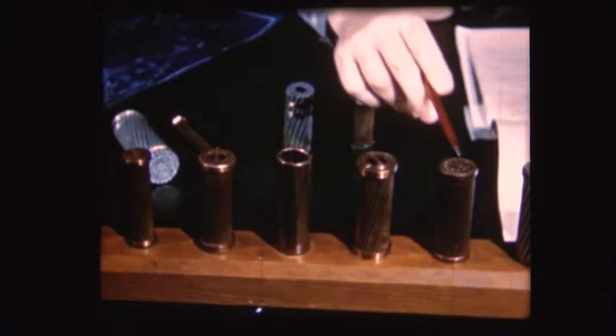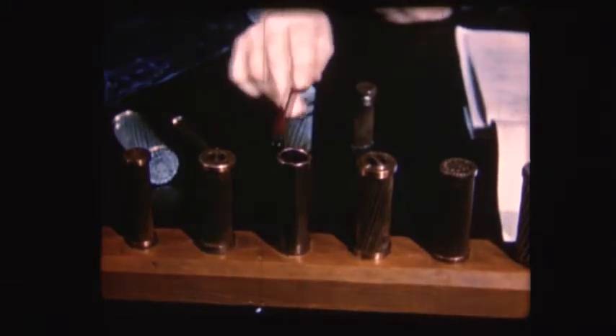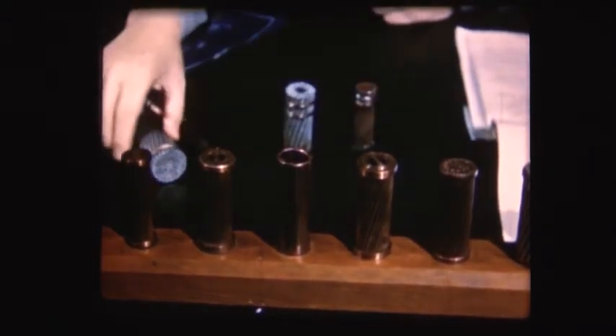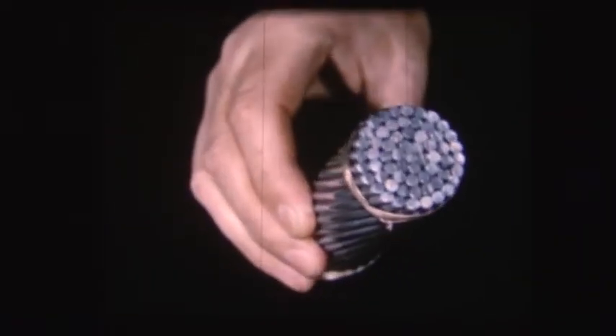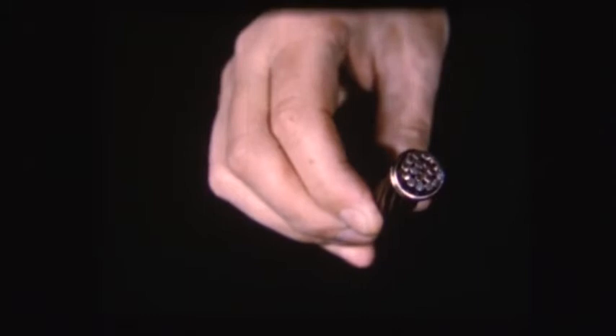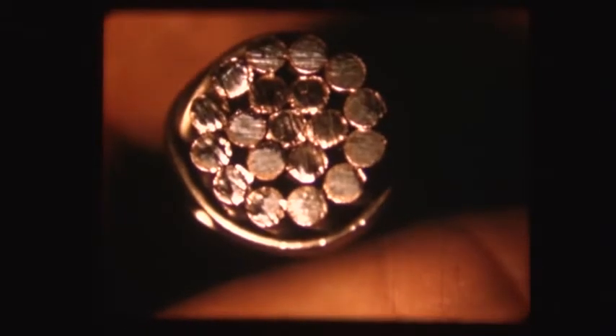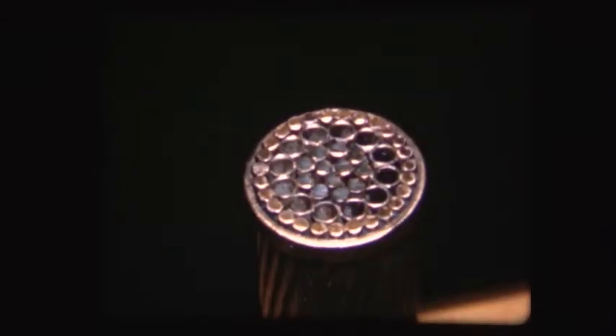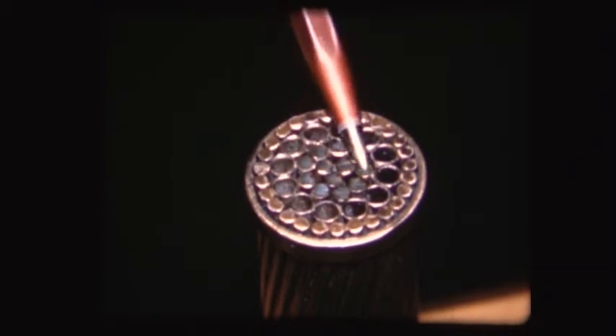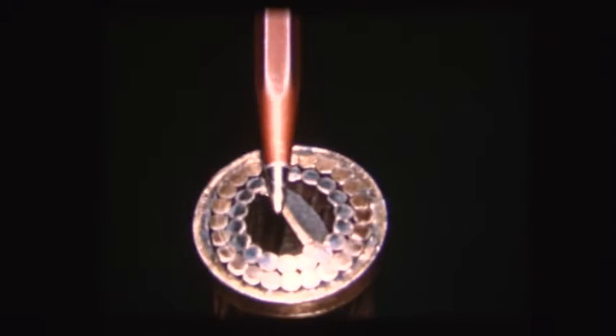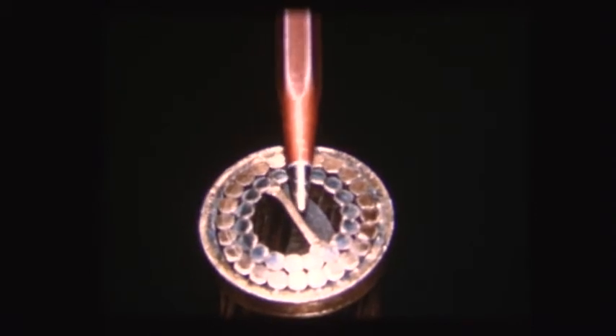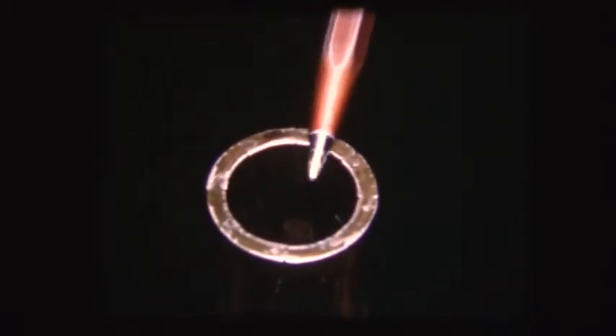There are a number of other types of conductor designed for special purposes. All aluminum conductor can be used in situations where high tensile strength isn't important. When extreme strength is needed, copper clad steel may be used. This conductor is made up of steel strands coated with copper by a molten weld process. Another type uses copper strands around a copper clad steel core. Expanded copper is available in several designs, either with or without steel reinforcement.